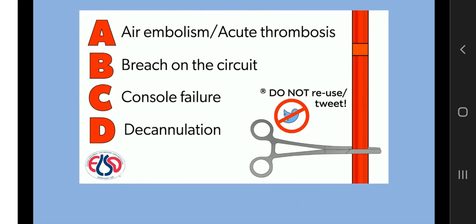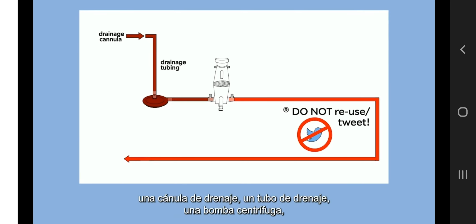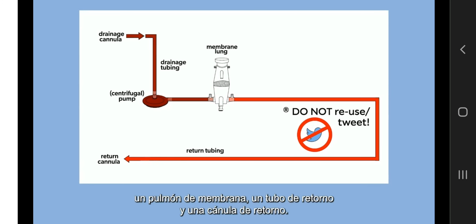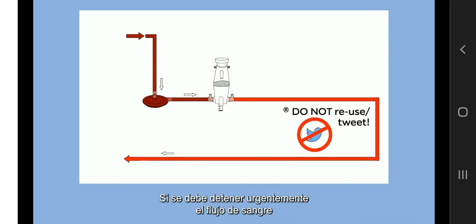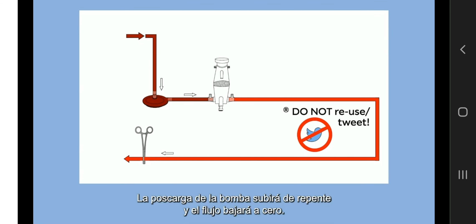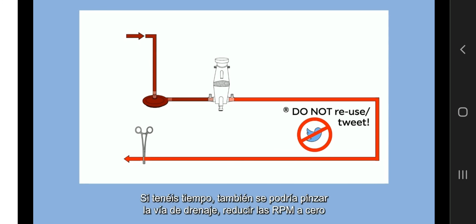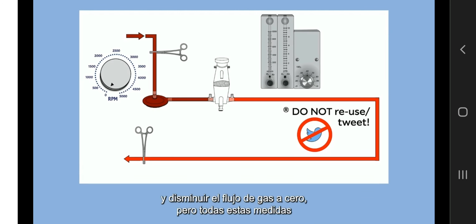And this is the schematics of a basic ECMO circuit: a drainage cannula, a drainage tubing, a centrifugal pump, a membrane lung, and a return tubing, and a return cannula. And this is the direction of the flow. If you need to emergently stop blood flow with the centrifugal pump in use, you just need to clamp the return tubing. Pump afterload will suddenly rise and the flow will decrease to zero. If you have time, you could also clamp the drainage line and decrease RPM to zero and decrease fresh gas flow to zero, but all of these are not strictly required.